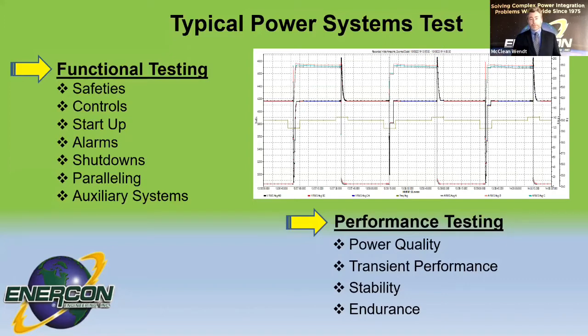So after we're sure that all of our protections are working correctly, then we can go into paralleling. If the system is set to parallel with other power sources, or if the system itself has multiple power sources, multiple generators in there, we'll do paralleling, make sure that each source can synchronize to each other or to an external source, and that they're sharing load properly. And then finally, auxiliary systems, make sure the jacket water heaters work, battery charging system, all of the things that are there to support the primary purpose of the power system are all in working order.